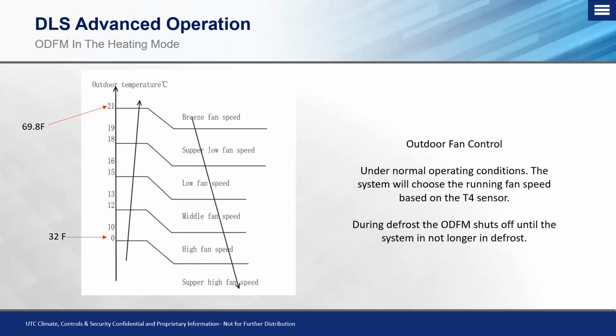Now we switch over and look at that fan motor in the heating mode. So just like we did in the cooling mode, we're looking at outdoor temperature to dictate fan speed. For outdoor fan control, under normal operating conditions, the system will choose the running speed of that fan motor in heat based on the T4 sensor, or our outdoor temperature sensor, just like the cooling mode.